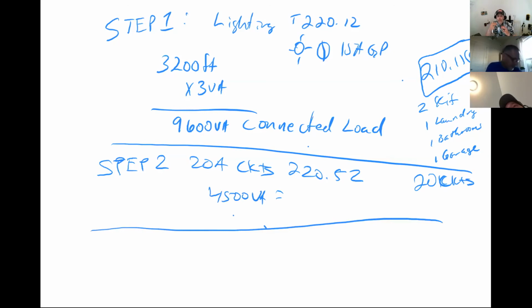Now both of these 2 items are considered connected loads. We are going to add the 4500 for the 20-amp circuits and the 9600 we had for the lighting and the 15-amp general purpose receptacles together.